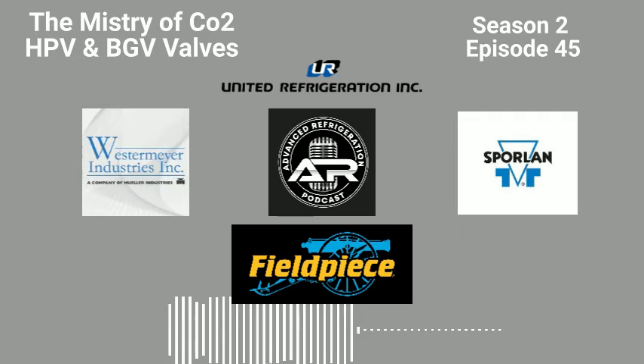Go ahead, Brett. I'm assuming that's why a lot of those cases have heat exchangers inside, right? To try to get any additional subcooling it could potentially get. So twofold. They're robbing Peter to pay Paul. They're trying to get a little bit more subcooling, and they're trying to keep any liquid from coming back to the medium temp / low temp. So yeah, they do help. Like Brett said, there are heat exchangers, or they make their own heat exchanger to weld the lines together.